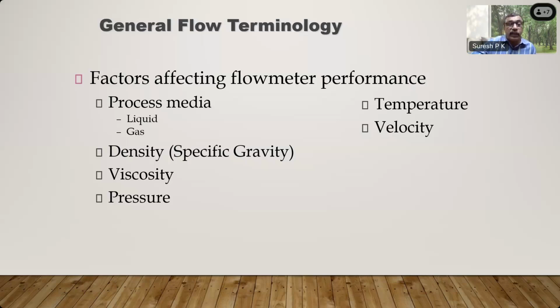What is the density range which you will encounter? What is the viscosity range? You cannot give a single particular value, but you can give a range. For example, if you are measuring crude, the crude viscosity might range from 13 centistokes to 100 centistokes. So the density, viscosity, pressure and temperature matter, because temperature can affect your viscosity also. As temperature increases, viscosity decreases for liquids and increases for gases.